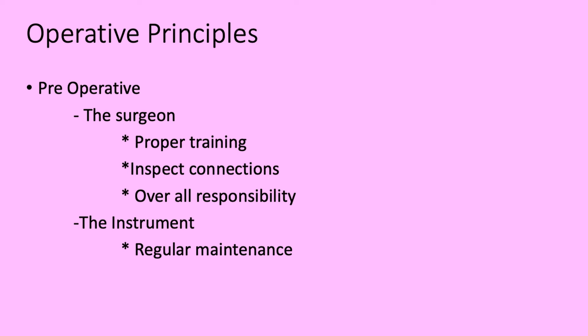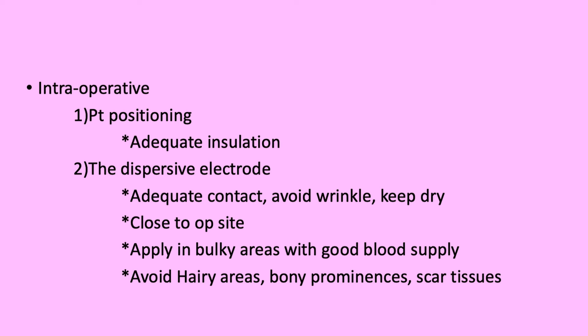Preoperatively, the surgeon should have proper training, inspect all connections, and takes overall responsibility of the procedure. The instrument should undergo regular maintenance to avoid injuries. Intraoperatively, the patient should be positioned properly and there should be adequate insulation. The dispersive electrode — the pad placed underneath the patient — should have adequate contact, avoid wrinkles, and be kept dry.